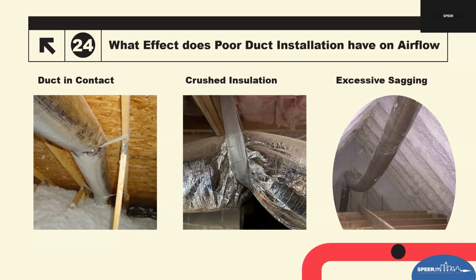Right now it just says use the approved strapping material, which has gone to a 2-inch wide strap, not a 1.5. That's the correct strap that we're looking at. It's not a noose style, it's just a sling, which is acceptable, but for some reason it has heavily crushed the outer insulation of the duct.